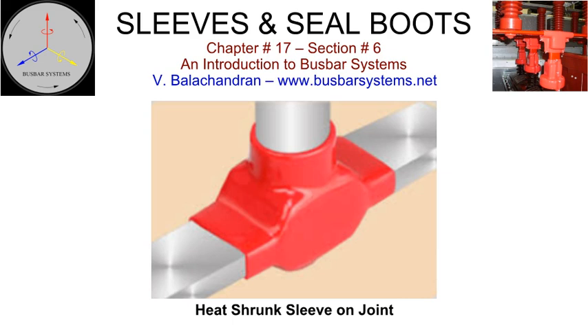Bolted joints must have coordinated boots that are fit for purpose. The thermal class of the insulating sleeve should be minimum class B, which more than meets the specified maximum hotspot temperature of the conductor in an enclosed bus.